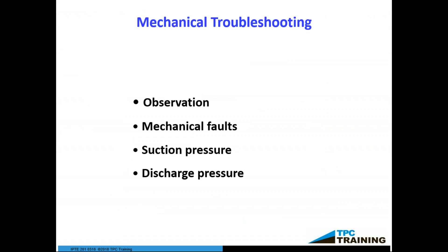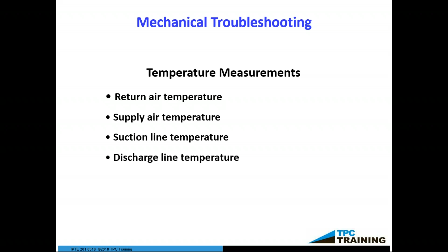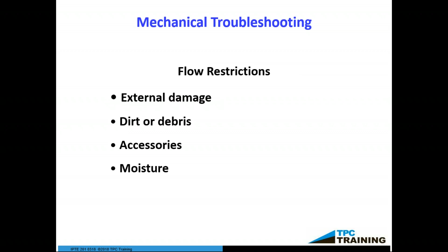Mechanical troubleshooting, we make observations. We look at mechanical faults. We look at suction and discharge pressure on HVAC to tell us what's going on with the system. We take temperature measurements: return air temperature, supply air temperature, suction line temperature, discharge line temperature. Then we look at flow restrictions, external damage, dirt or debris, accessories, moisture, you name it. And we look at the power supply, controls and safety switches, system switch, thermostats, high temperature limit switch, low pressure switch, high pressure switch, access door switch, defrost controls, outside temperature switch. Now, if the access door switch has failed and nothing works, where do you even think about going to look for that, right?